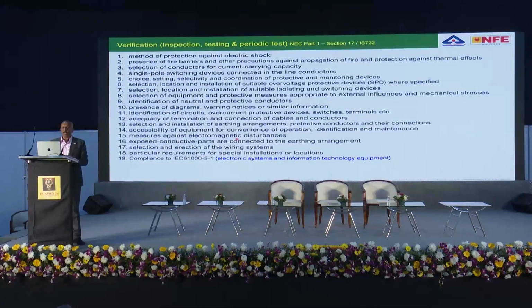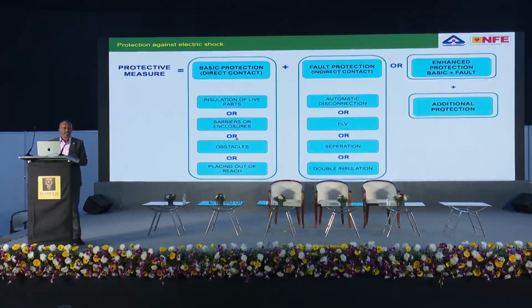For example, the first one, protection against electric shock, is achieved by many measures. Depending upon the location, say for example solar PV, you have to adopt double insulation. Let's say a furnace, you have to adopt another method. Depending upon the location, you have to understand what the safety measure is and where it is applied, and the first inspection itself is to check whether these measures are implemented properly. Like this, there are 19 inspection measures. I am sure India will take at least the next 10 years to learn about this completely, because these are from the IEC standard. Most of the developed nations have been following it for 40-50 years. During these years, they learned a lot. They know what to do, whereas in our case, we will take time to learn about it.